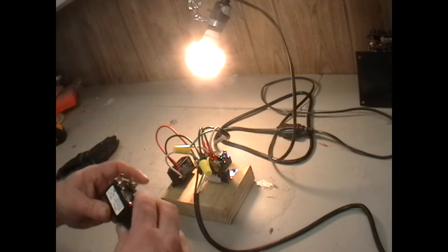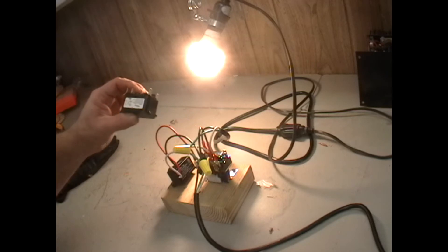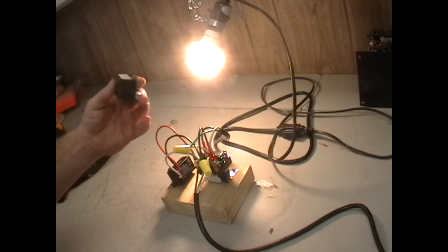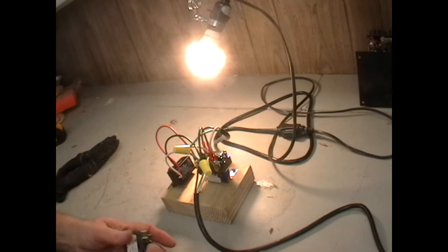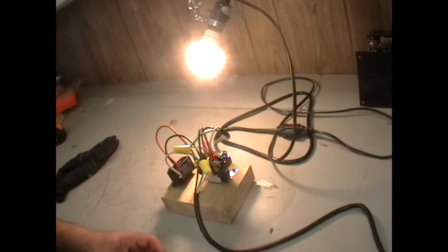I always say 24 volts because I'm an air conditioning guy, but most of these peanut relays that we run across in the field will be 24 volts, and a lot of fan relays are 24 volts. But you have to make sure it's 120 volts because you can't send 120 volts from a photocell to a 24 volt relay.